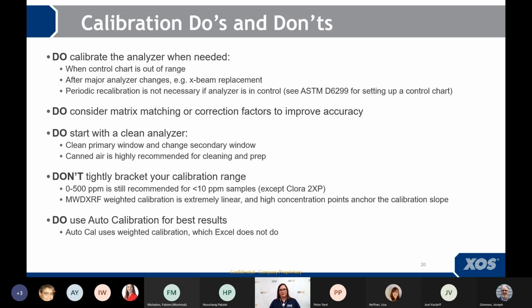And there is a purpose for these higher calibration points. They actually serve to anchor the calibration slope, and you'll reduce some of the error in the intercept. So there's a reason that you're calibrating this high. And of course, lastly, make sure you use auto calibration for best results so that you can take advantage of that weighted calibration, which your standard Excel doesn't do. But we have a workaround for that as well.